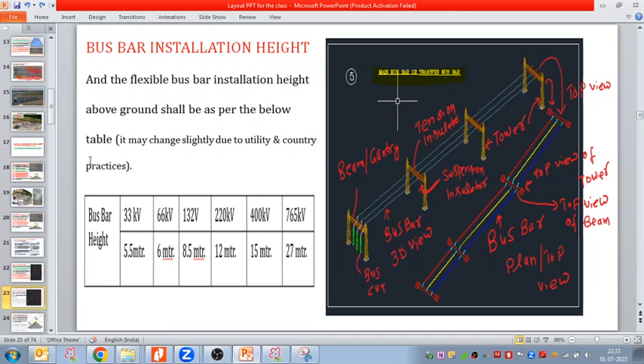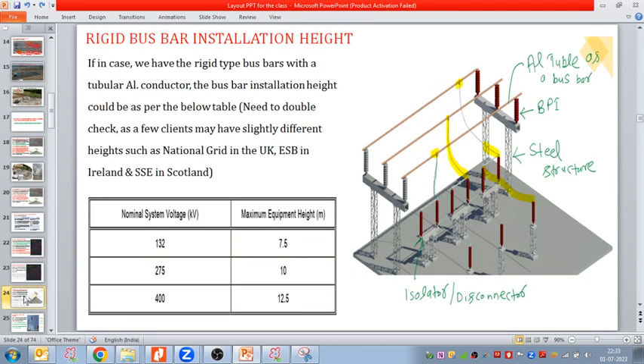Are the same height values applicable for rigid bus bar also, sir? No, I'll come to the rigid bus bar next. When we have the rigid bus bar, it looks like this - it appears like this. If we have the rigid type bus bar with a tubular aluminum conductor, the bus bar installation height could be as per the table below.